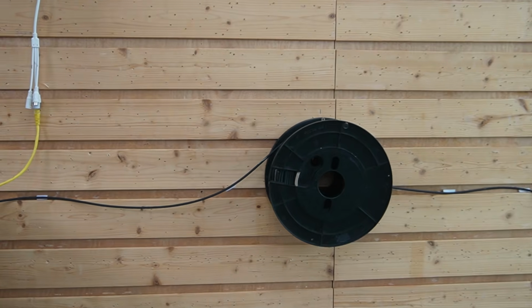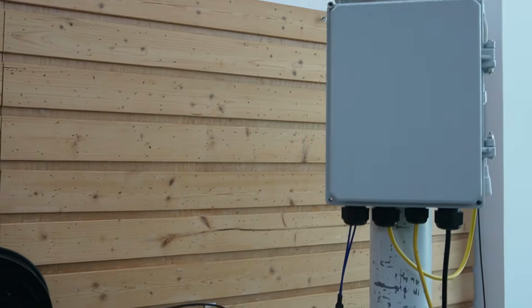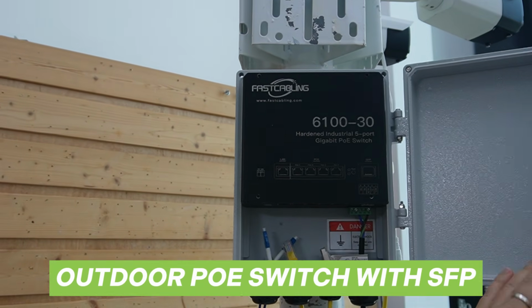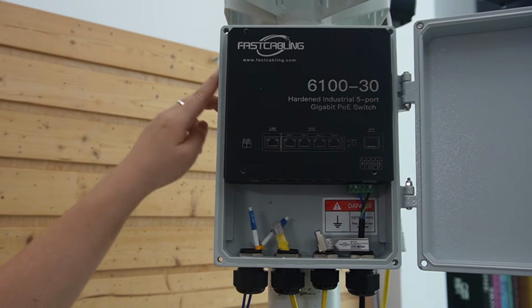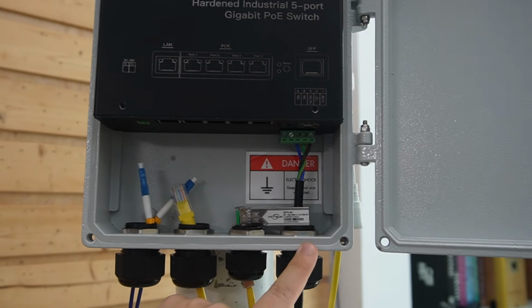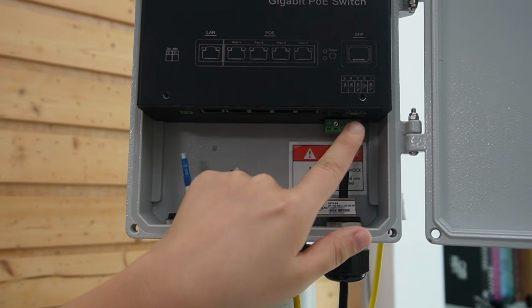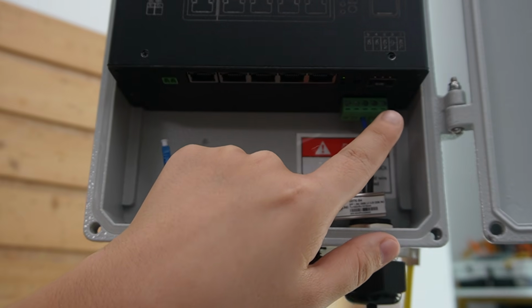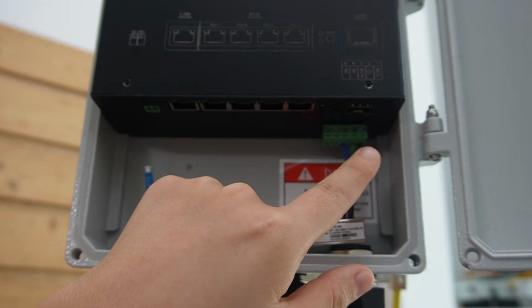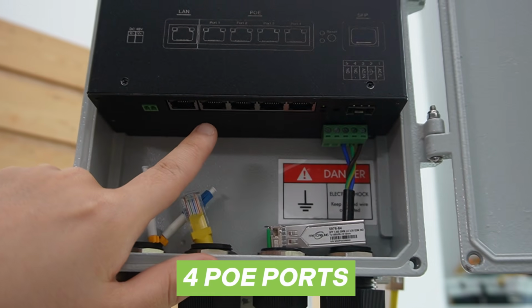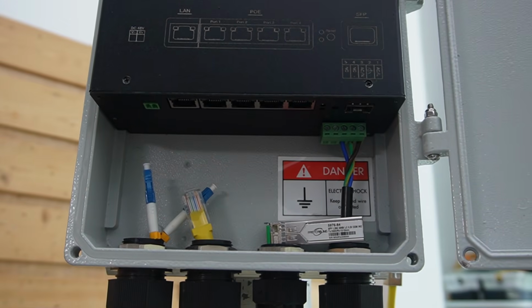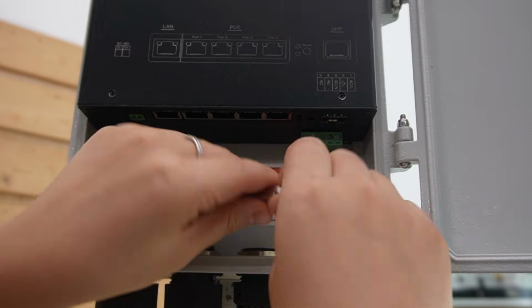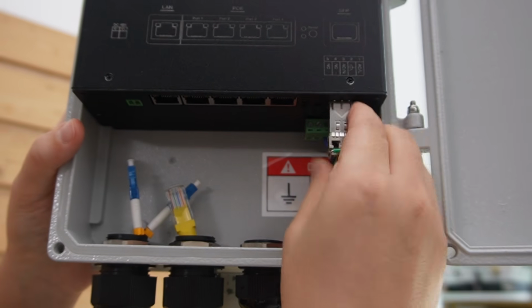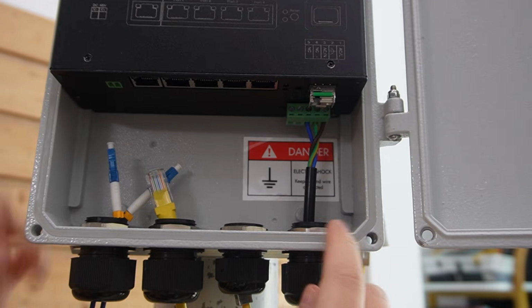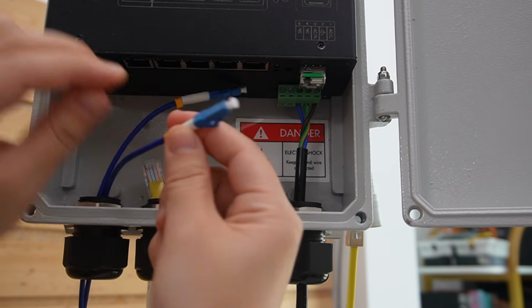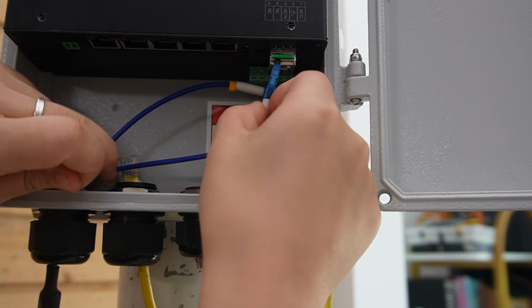The fiber runs from the control room all the way to the pole. Now let's get to the pole, where we have our outdoor PoE switch with SFP. This is a rugged IP67-rated metal enclosure designed for outdoor use. It has 1 SFP slot on one side, where our fiber optic cable connects, and it also has 4 PoE ports. The fiber brings the data in, and the switch converts it back to electrical signal. Again we need our SFP transceiver, matched as a pair. Slide it into the SFP port. Remember, we used strand B, don't connect the wrong one.